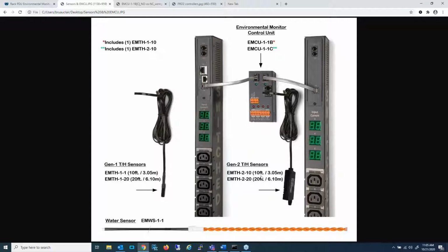Plus, it is more accurate on the temperature accuracy versus the older sensors. The relative humidity accuracy with the older sensors versus the new sensors has not changed. So directly, the PDUs support only combination temperature and humidity sensors. But if we take a look up top here, we have what we call an environmental monitor control unit, or EMCU for short, and that is this device in the middle.